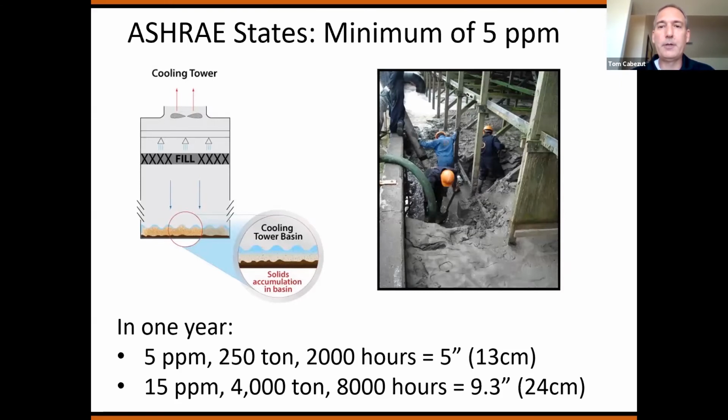This is a real picture. This was done on a field-erected cooling tower overseas that is close, obviously, to a very dirty and sandy environment. So if you're not able to filter that material, this is what the guys have to do out in the field. Nobody likes to do it, and it's not a fun process at all. I've been in a number of towers myself.